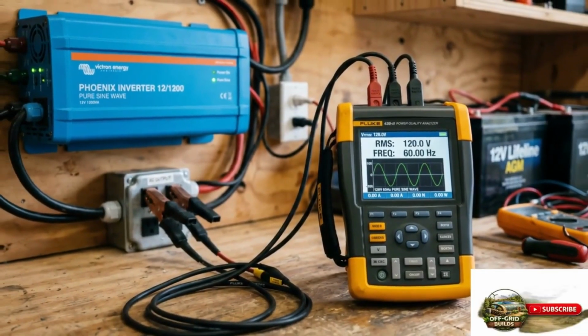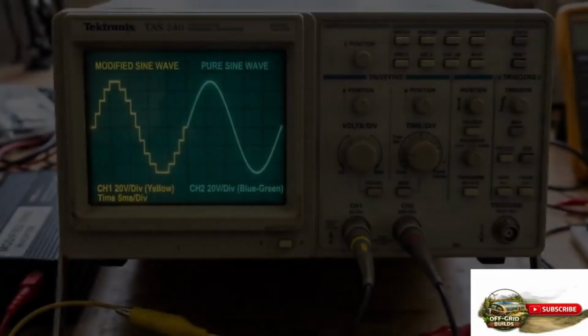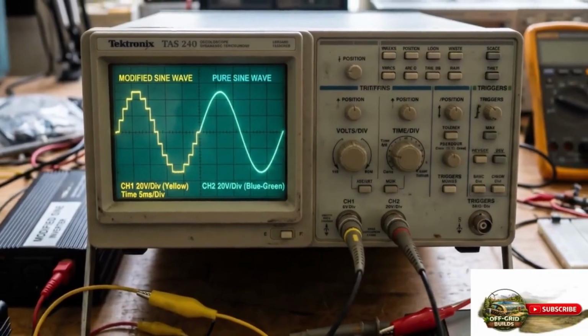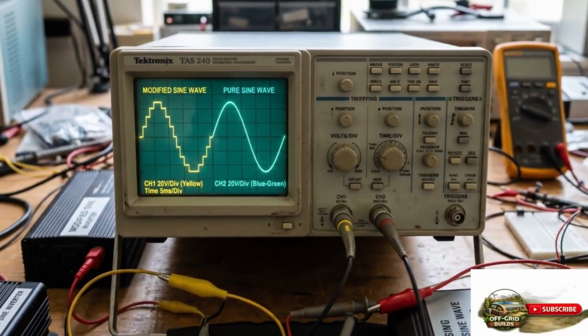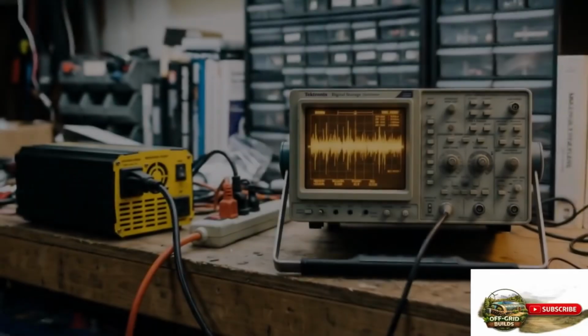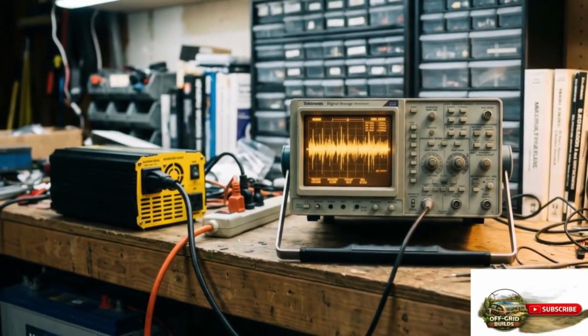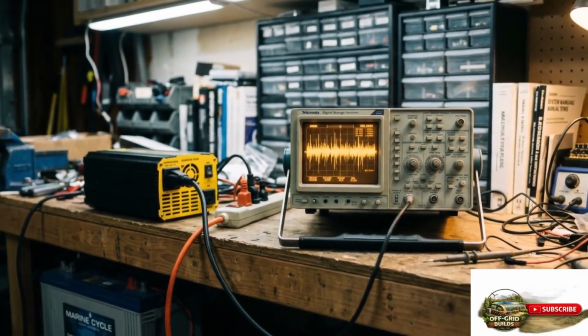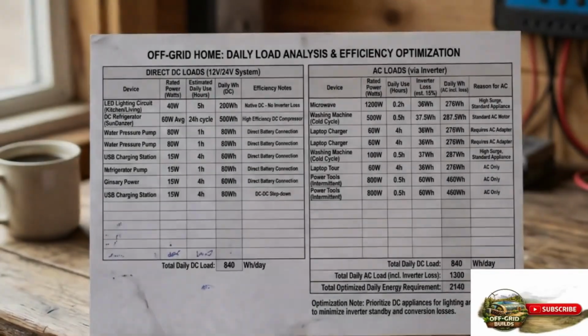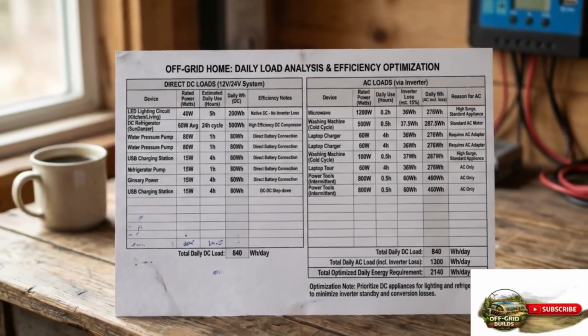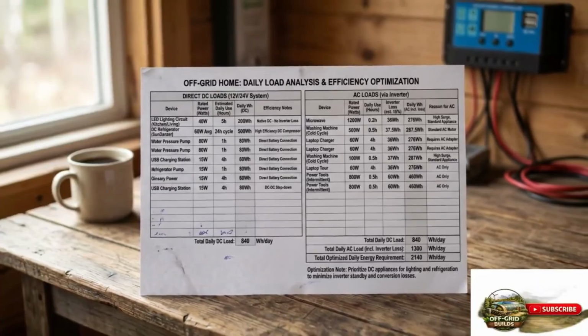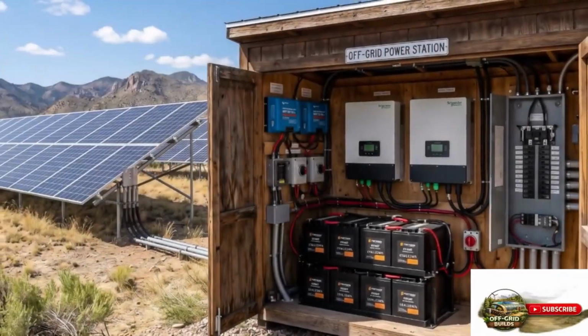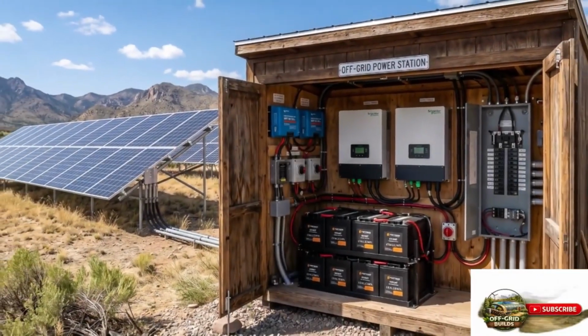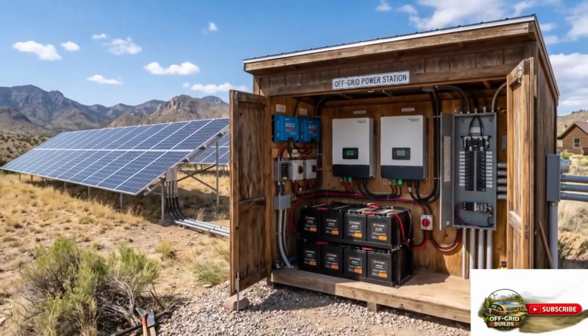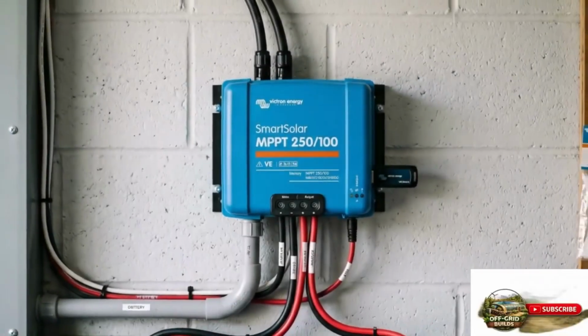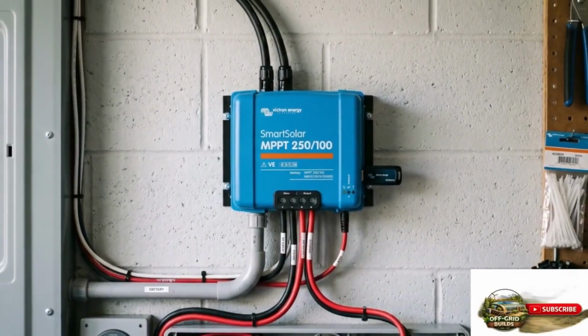A 12-volt or 24-volt DC refrigerator or freezer operated directly from the battery bank through a DC to DC converter is more efficient than running a standard AC refrigerator through the inverter. LED lighting can be operated on DC with appropriate fixtures. Water pumps designed for DC operation are available. In a 10,000-watt off-grid system, where efficiency matters across a full year of operation, identifying which loads can be served directly on DC and which require AC conversion is worth the analysis.